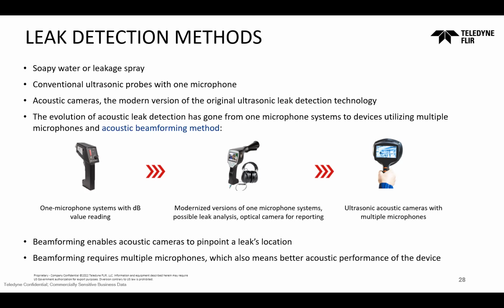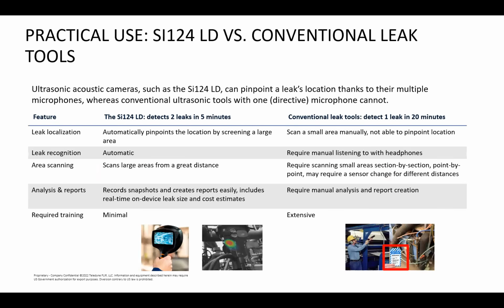From this point of view, acoustic technology performs best for leak detection. In maybe 95-98% of cases, since our detection threshold is quite low, the camera works as well as directional microphones, even though some sniffers and directional microphones can find really small leaks, especially for gases. But our camera finds a large scope of the leaks that happen in the industry, so we can claim we have the best solution.